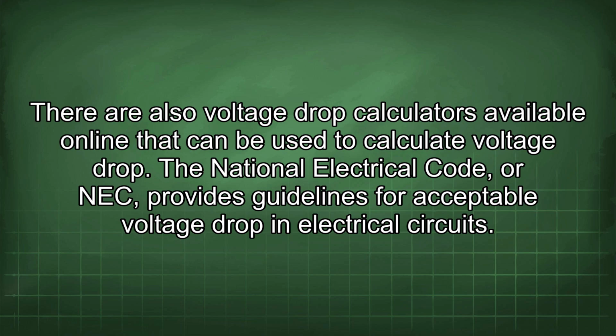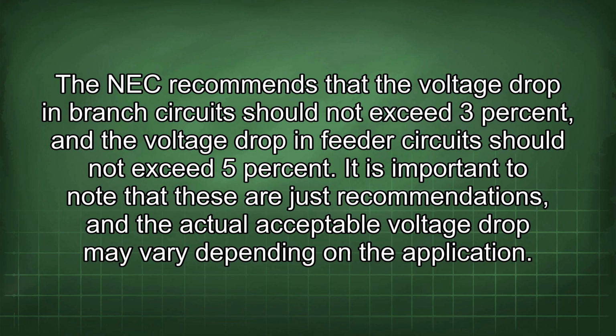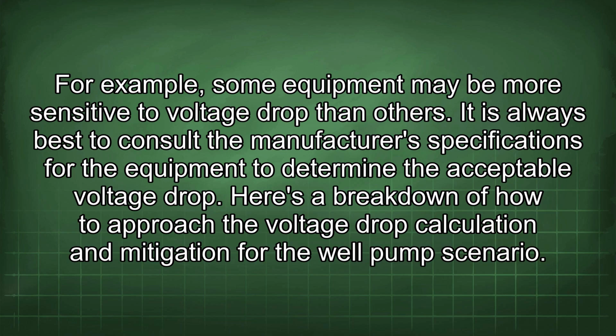The National Electrical Code, or NEC, provides guidelines for acceptable voltage drop in electrical circuits. The NEC recommends that the voltage drop in branch circuits should not exceed 3%, and the voltage drop in feeder circuits should not exceed 5%. It is important to note that these are just recommendations, and the actual acceptable voltage drop may vary depending on the application. For example, some equipment may be more sensitive to voltage drop than others. It is always best to consult the manufacturer's specifications for the equipment to determine the acceptable voltage drop.